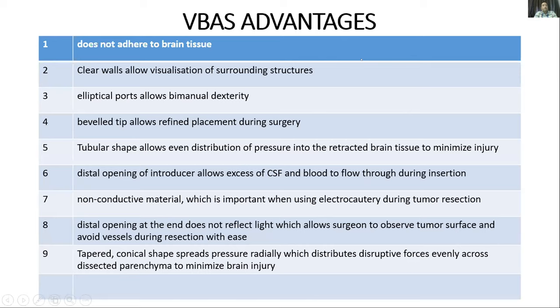The ViewSite Brain Access System has several advantages: it does not adhere to brain tissue; clear walls allow visualisation of surrounding structures; elliptical ports allow bimanual dexterity; bevelled tips allow refined placement during surgery; its tubular shape allows even distribution of pressure on retracted brain tissue to minimise trauma. There is a distal opening allowing CSF and blood to flow through the insertion site. It is made of non-conducting material, important when using electrocautery. The distal opening does not reflect light — unlike many retractors — preventing obscured views of tumour surface and vessels, thereby avoiding vascular and brain tissue injury.